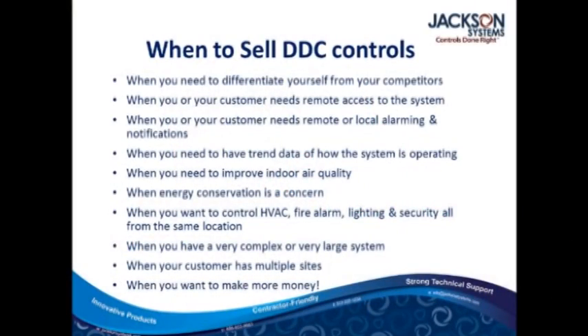If you've got 40 thermostats around the building, chances are after a short time, somebody set one up to run late because they were going to work late and didn't set it back. Nobody's really checking them. So after a period of time, the programmable thermostats, if there's a bunch of them, would tend to not be programmed anymore. It becomes a hassle and nobody's really thinking about it.